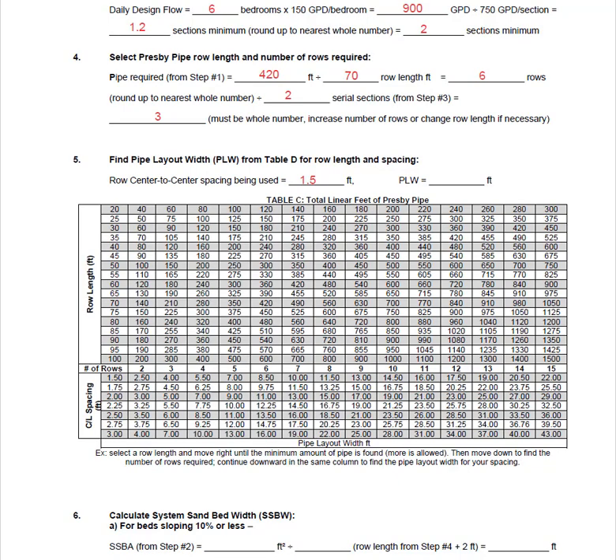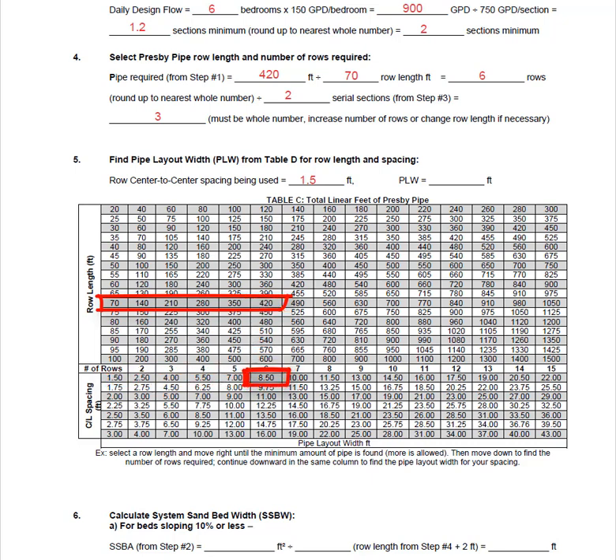We are now going to determine the dimensions of our field, starting with the pipe layout width. We will locate our row length — 70 feet — and move to the right until we find the total amount of pipe required, 420 feet. Now we move down this column until we reach the row indicating how many rows are required — six as previously determined. Then we continue down until we are in line with one and a half foot center-to-center spacing. Where our chosen spacing and our row length column intersect, we find our pipe layout width of eight and a half feet.